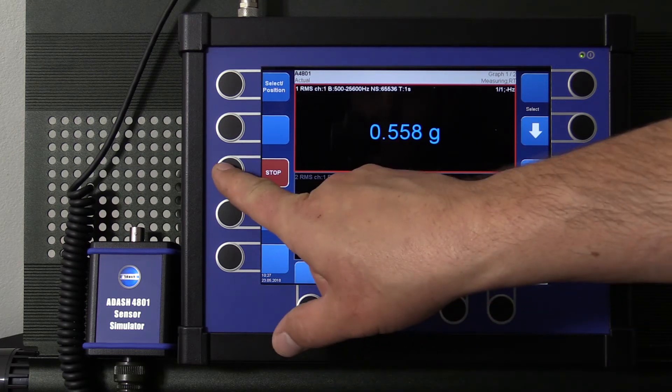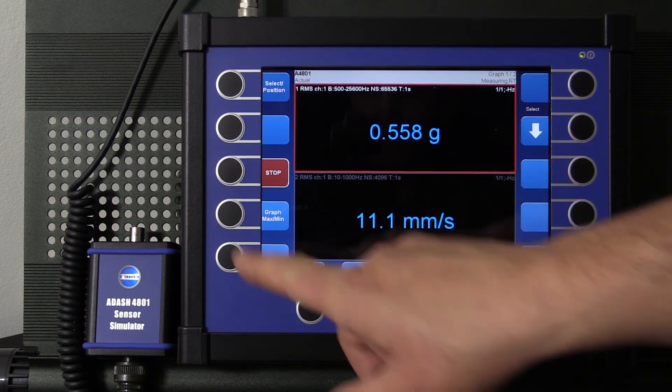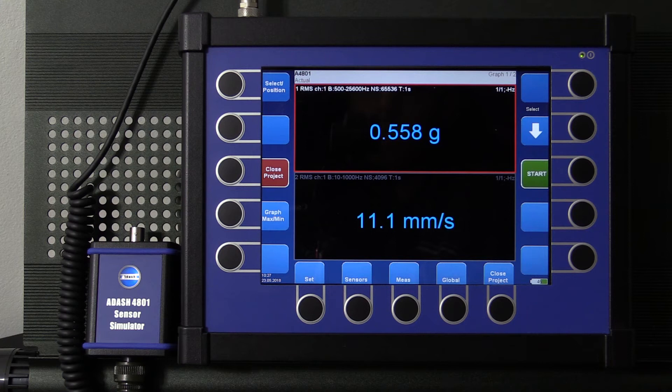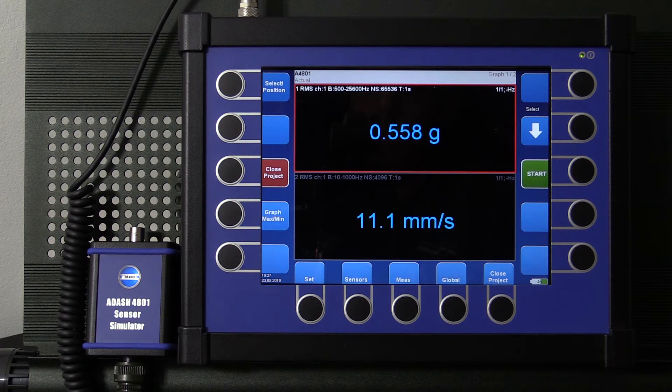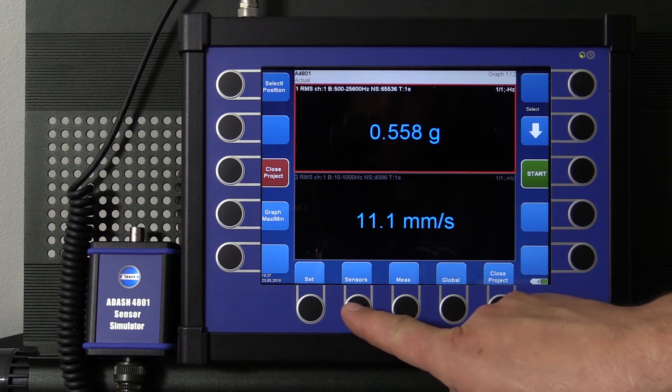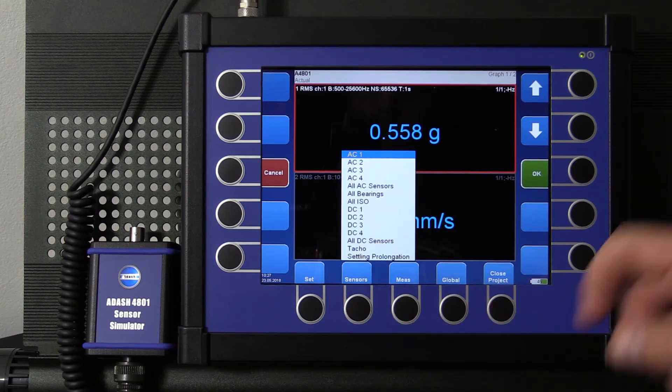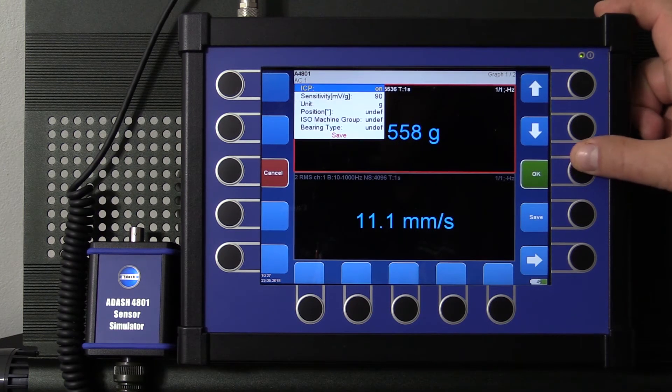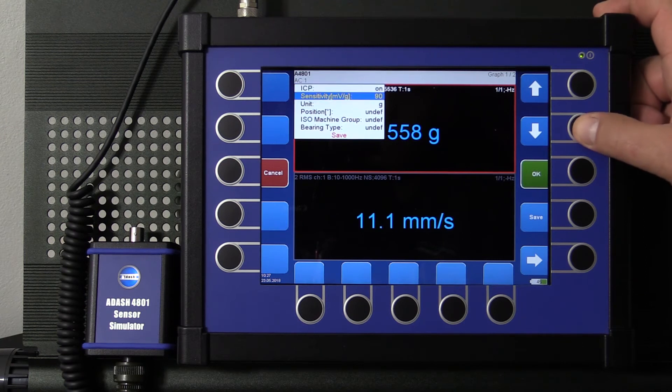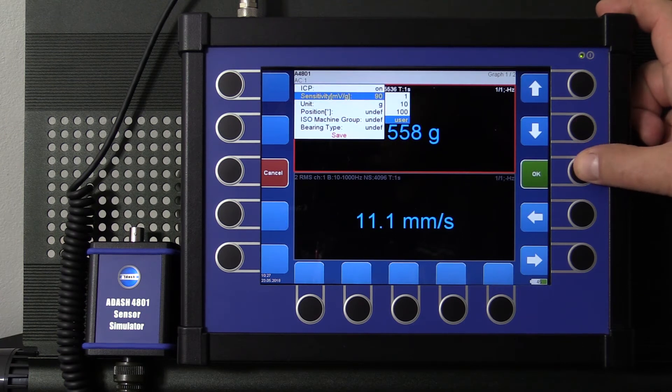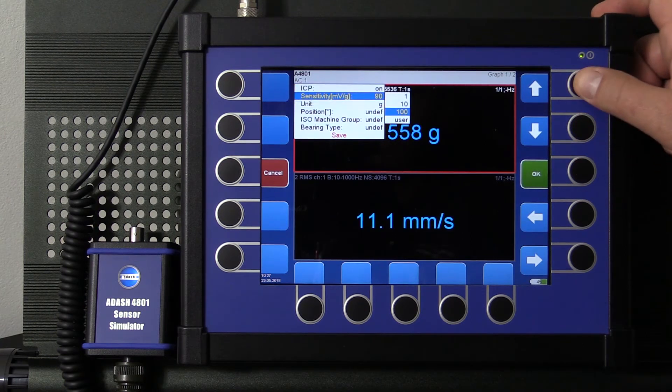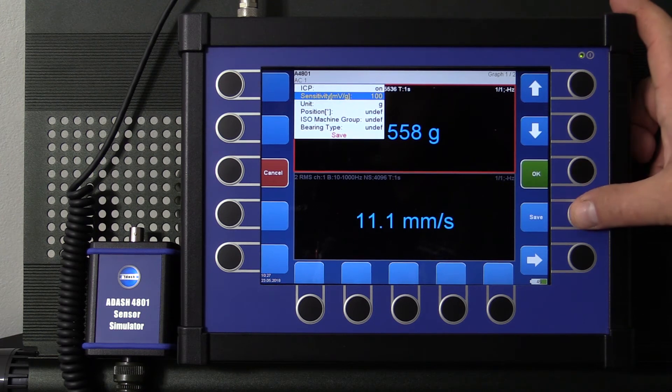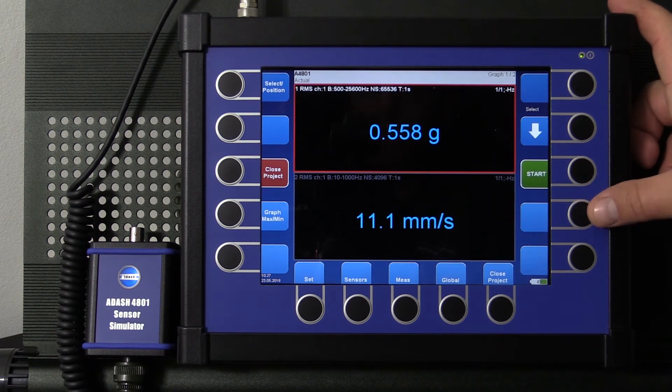I did this on purpose. Remember that the values on Sensor Simulator are for 100 mV per G sensitivity. What sensitivity we have preset in the analyzer? Let's take a look. Ok, we have 90 mV per G here. So we will change it into 100 and start the measurement again.